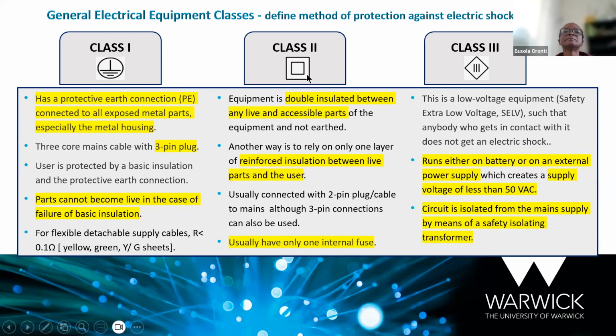For the class 2 device, you don't have a connection to the earth. What you have in this case is a double insulation between any live and accessible parts. Normally the plug will be a two-pin plug without any earth connection. So what will usually happen in that case is that between the user and the live parts, if there is a breakage of insulation, like we are saying there are 2 layers, it will only be one of the layers that will break down.